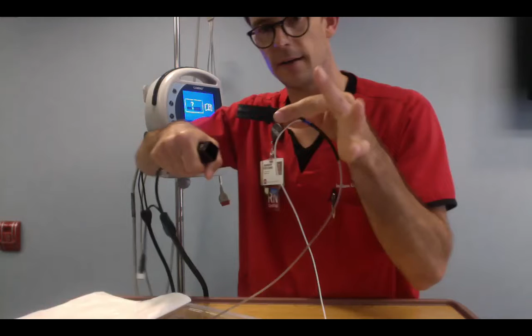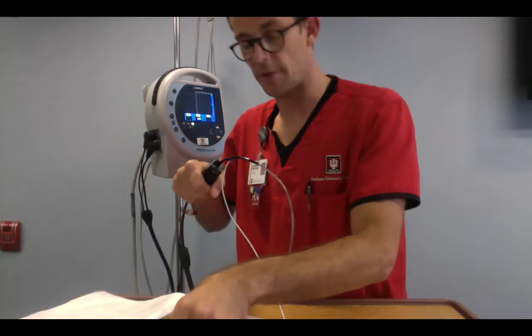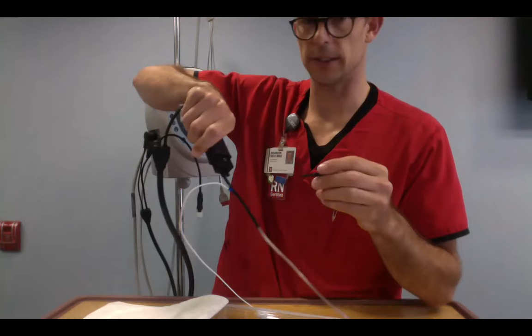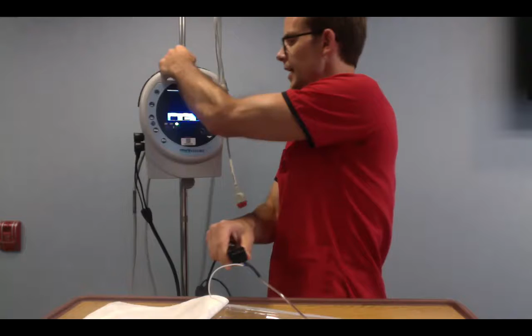So you have this side, the neurosurgeon has this side. They're going to plug it in before the fiber optic cable goes into the patient's skull to zero it to atmospheric pressure. Inside this kit is a tiny plastic flathead screwdriver, and on the surgeon's side is a little space for that to go to zero. Now, if this was a new catheter, it would give me an ICP and a green line here. And so the neurosurgeon would just turn this until that says zero.